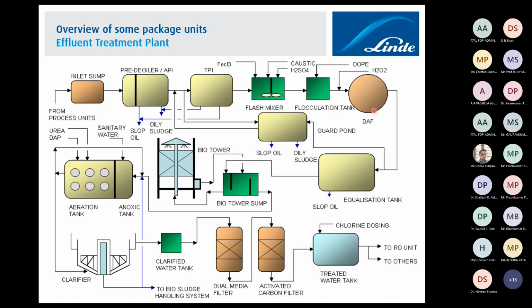And in the DAF unit, dissolved air flotation, we usually put a compressor inside it. When you put the compressor at the bottom, all the emulsified oil, along with the air bubbles, will form a small film surrounding the bubbles, and it will come to the surface. There are some surface skimmers that will remove the oil from the surface. So this is how additional oil can be removed. Typically up to 10 ppm, 10 parts per million, of oil can be removed from the DAF unit.